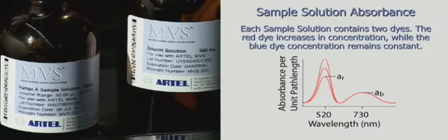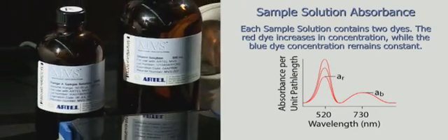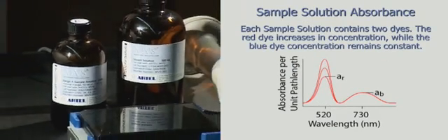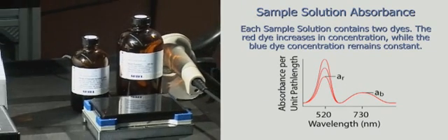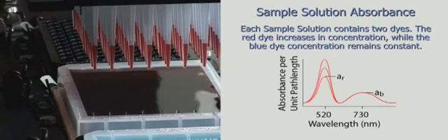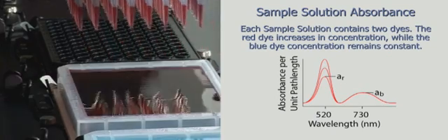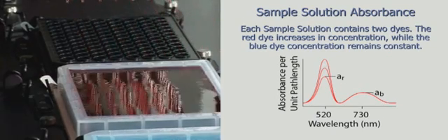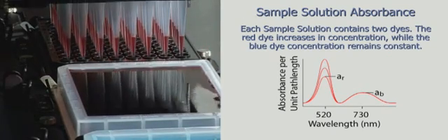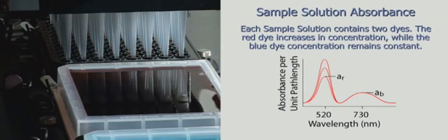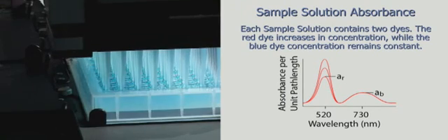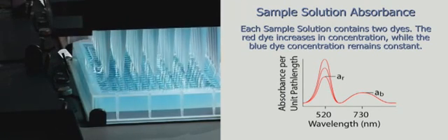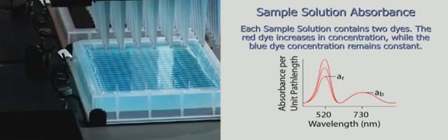The MVS uses two dyes, each with a separate absorbance spectrum. MVS sample solutions contain both red and blue dye. Different concentrations of red dye are used in the sample solutions to accommodate a range of volume deliveries from 100 nanoliters to 200 microliters. MVS diluent solution contains only blue dye.